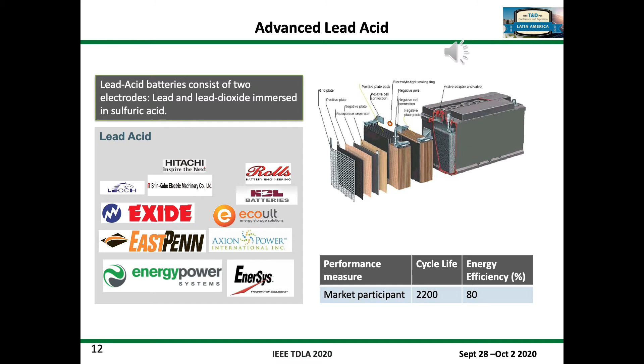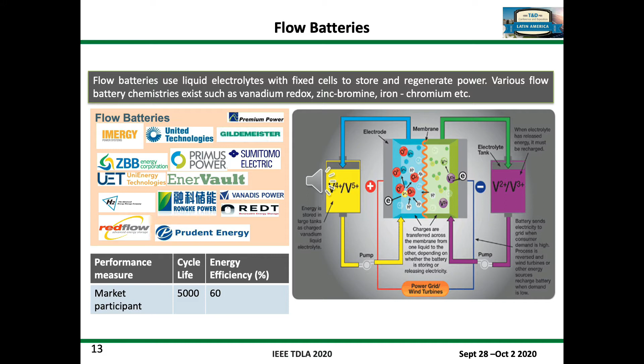Examples of flow energy storage include redox flow and zinc bromide. Flow batteries efficiency is in the order of 60%, quite low compared with lithium-ion. The system uses pumps to maintain circulation of the fluids within the tanks. Life cycle is similar to the lithium-ion batteries. Installations of this type are still at the pilot projects or research and development stage.